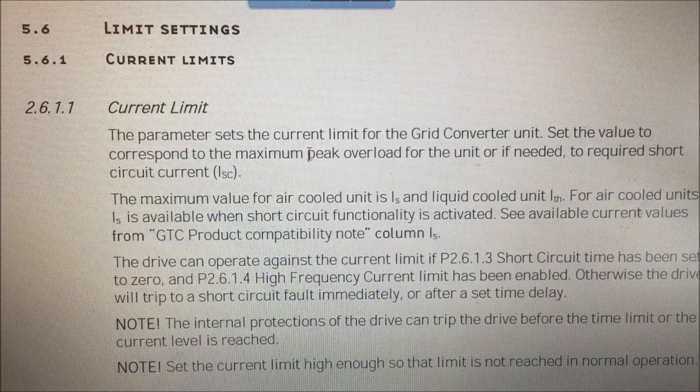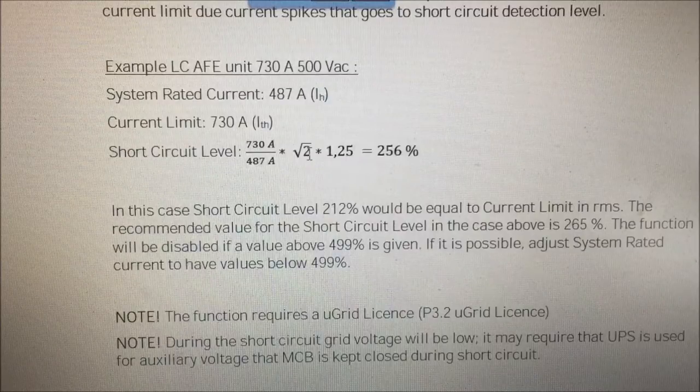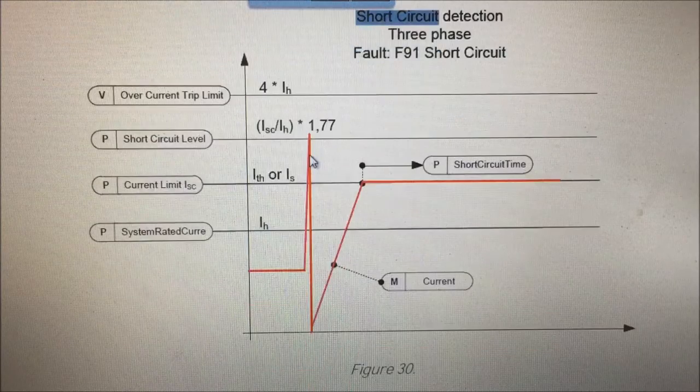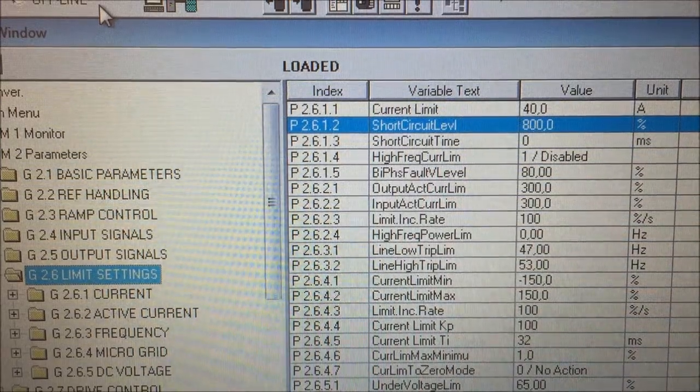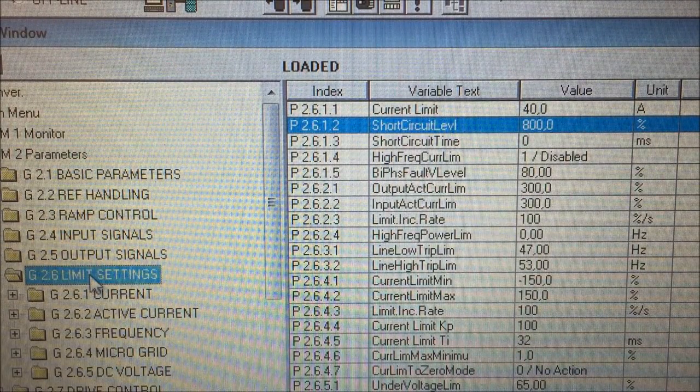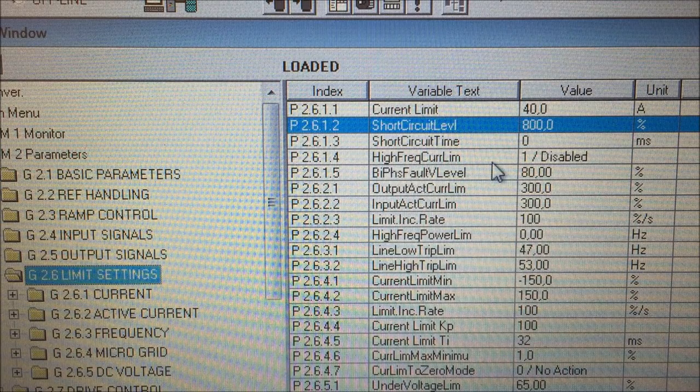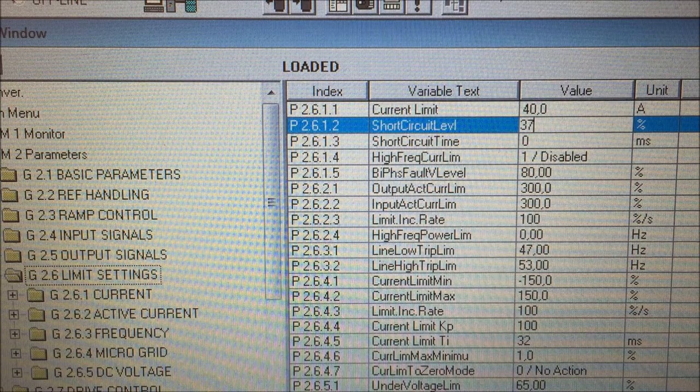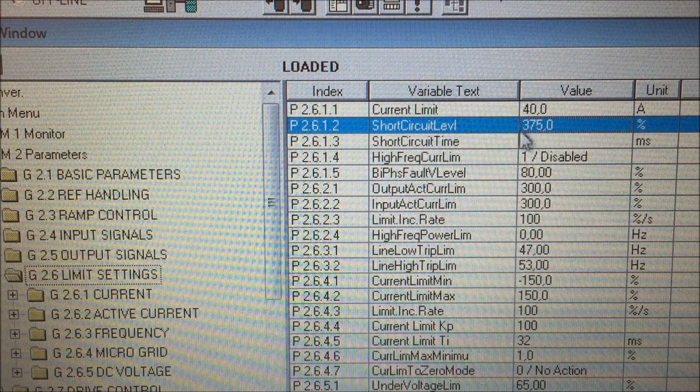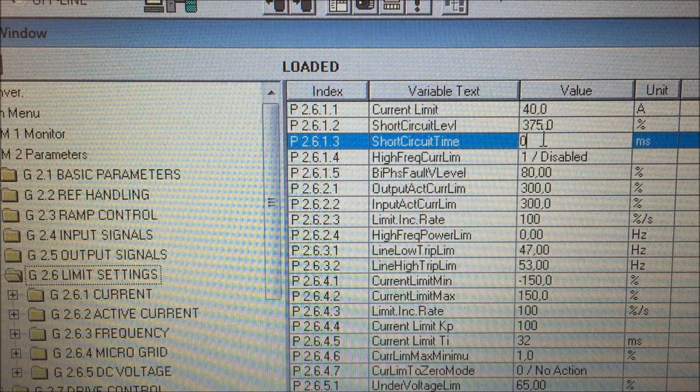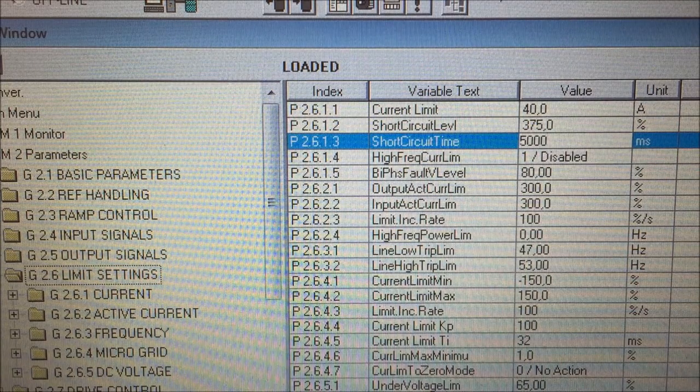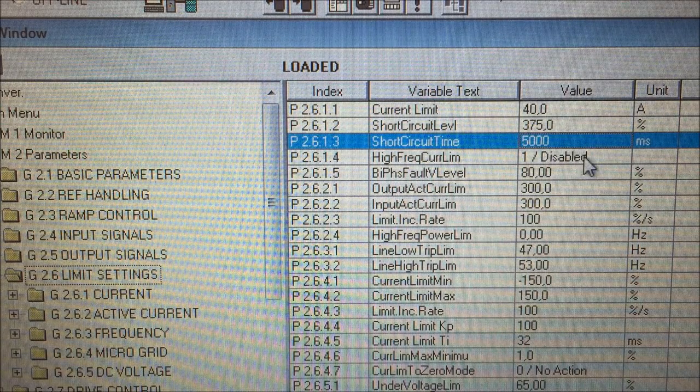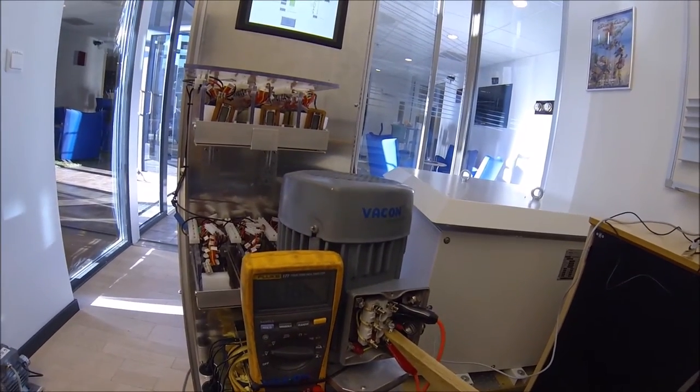In the microgrid manual the description for how to set the short circuit current levels, how to calculate it, is quite well described here. The parameters for the short circuit and the current limiter is set here. Limit settings, the fault is 800 and we calculated that this drive is 375, it's quite strong for short circuit. How long time should we keep the short circuit to blow the fuses? I know that this will take at least five seconds so this is five thousand milliseconds. Let's try that and the fuse is going to break instead.